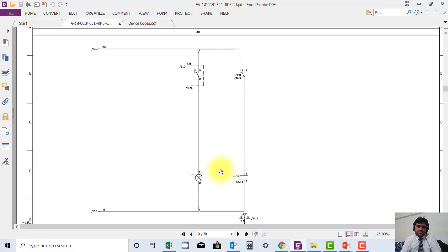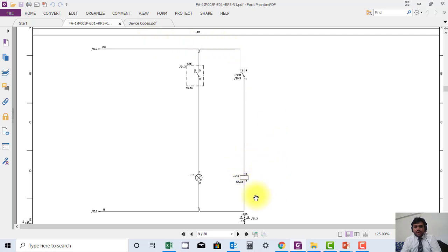At the end it gives alarm through AC supply. Because now DC has failed, the alarm will be fed through AC supply to the AC annunciator. This is the way they have done it.